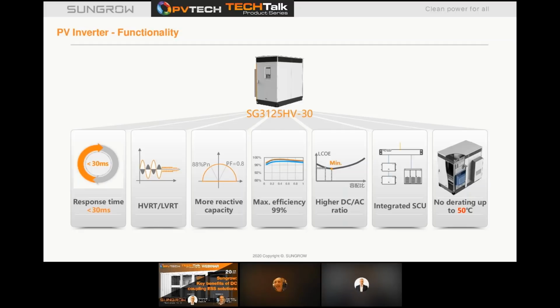As you can see, it can support and perform multiple grid functions, has a high efficiency rating due to the advanced 3-level technology, plus it has integrated zone monitoring functions for online analysis and troubleshooting. With the system cooling design, we can operate in temperatures up to 50 degrees Celsius and not experience any losses or derating. One of the highest in the market, allowing us to install the inverter in the most challenging of environments.